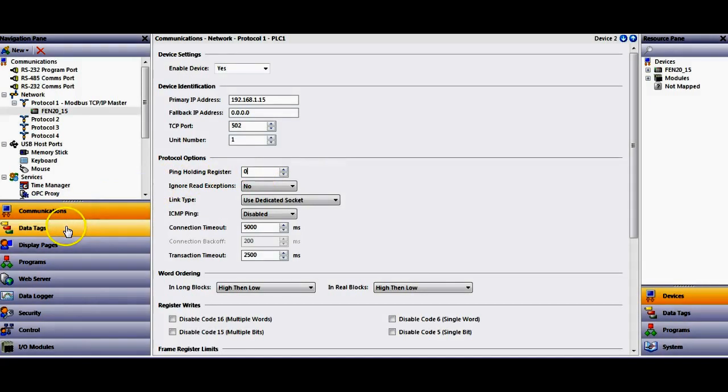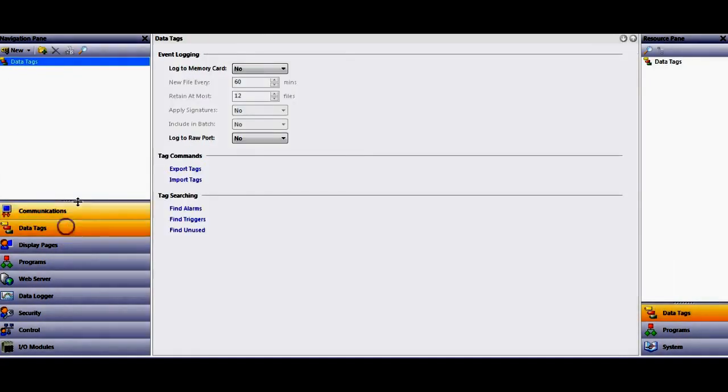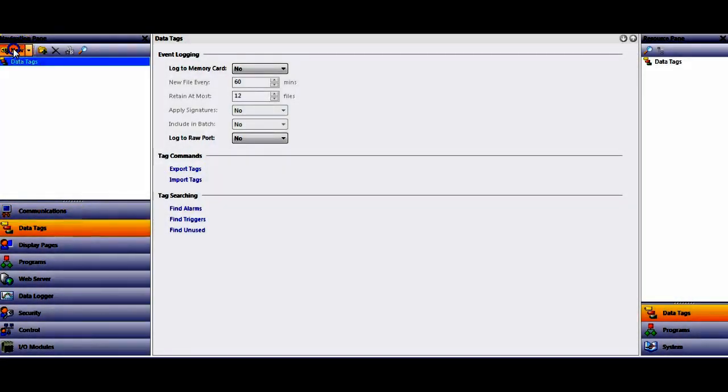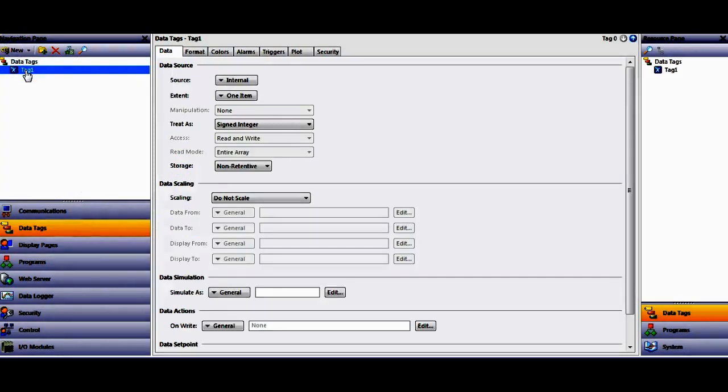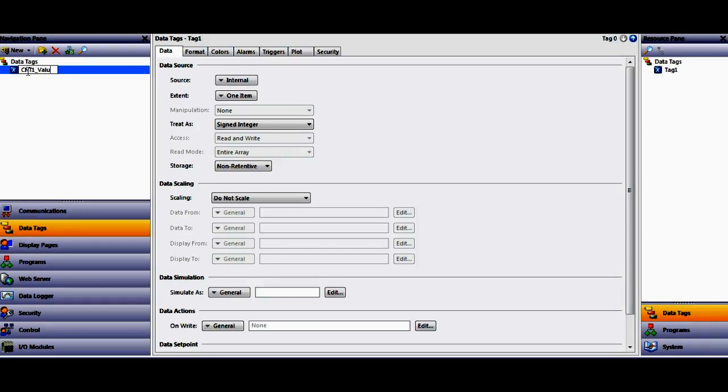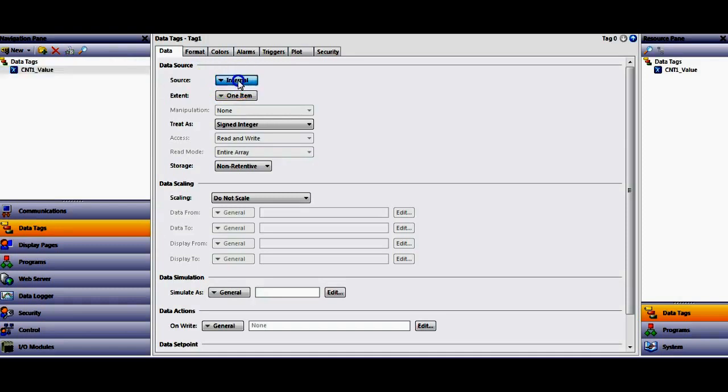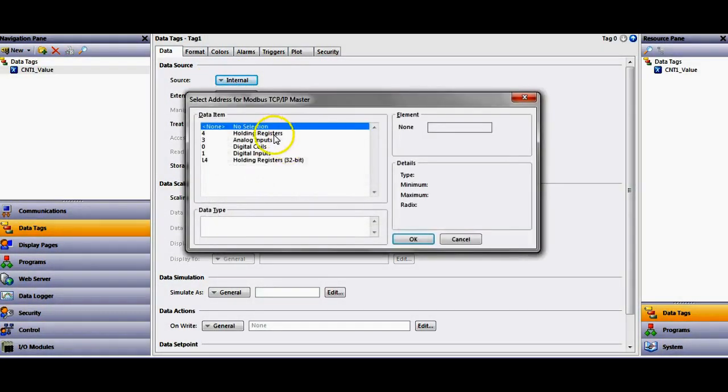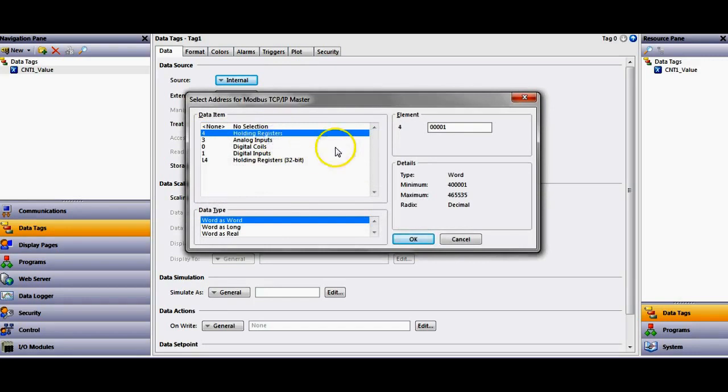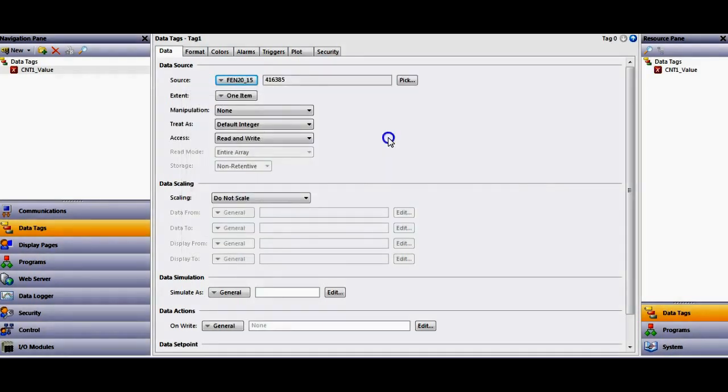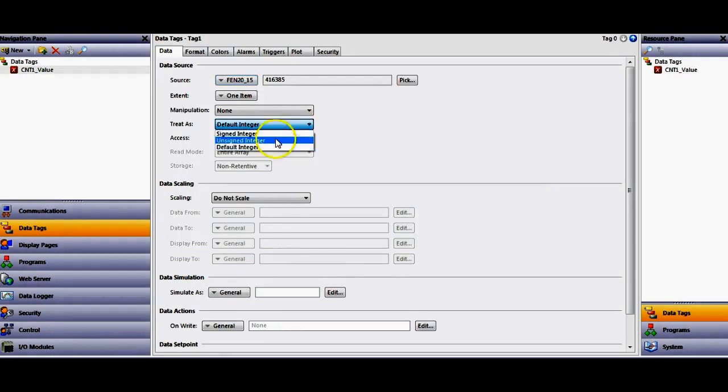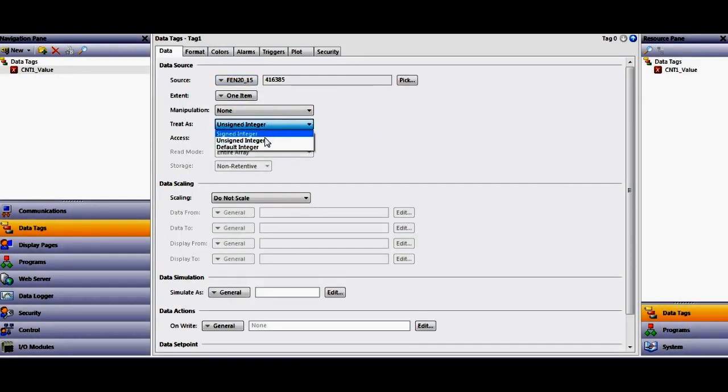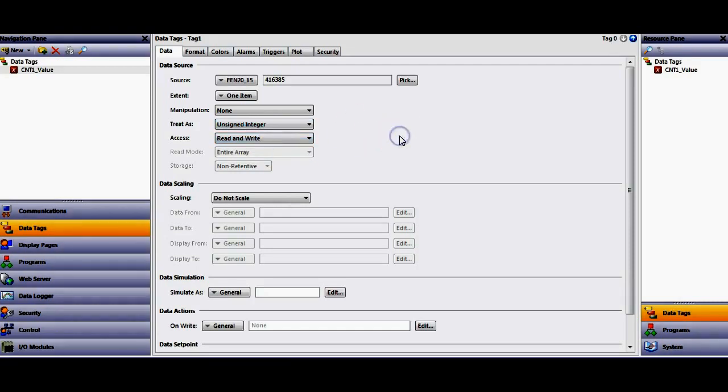And then if I go over here to Data Tags on the left, go to Data Tags. I'm going to create just a new tag. I'm going to rename this one CNT1 underscore value. I'm going to map this. Here's the trick. I'm going to map this. I'm going to hit the pull down here. I'm going to map this to the FEN20 holding registers. And then the data coming from the HMI is going to start at 16,385. There it is. I'm going to make it an unsigned integer. This default setting here actually acts as a signed integer, so I'm going to make it an unsigned integer.